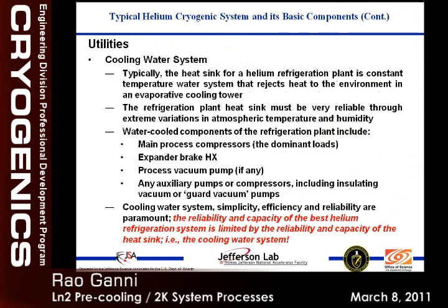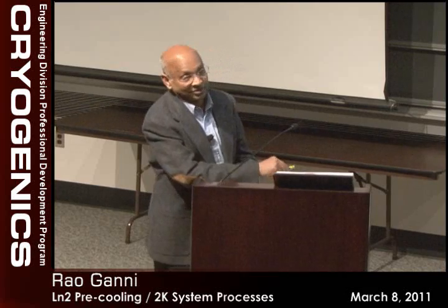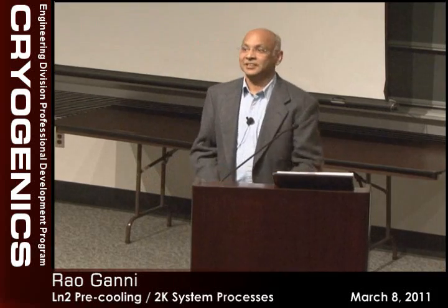Cooling water. And this is where we reject all our heat. And we don't pay a lot of attention because there are so many cooling towers. And the reliability of the cryogenic system mostly traces back to these three factors: cooling water, instrument air, and electric utility. And very strongly to cooling water. My analogy to cooling water is we can have a beautiful horse. If the horseshoe is not good, it can only run as good as the horseshoe. If the shoe is not good, it's not going to run. So that's what it is.